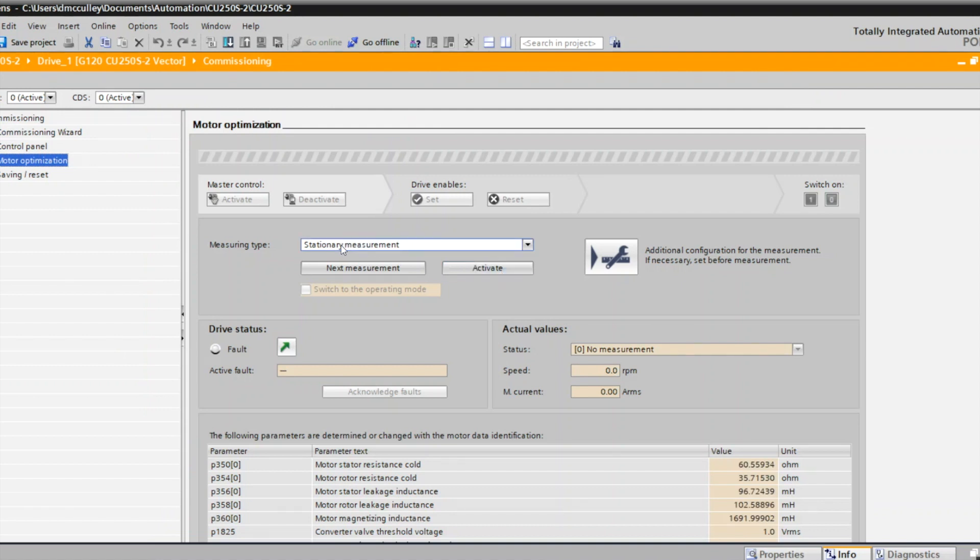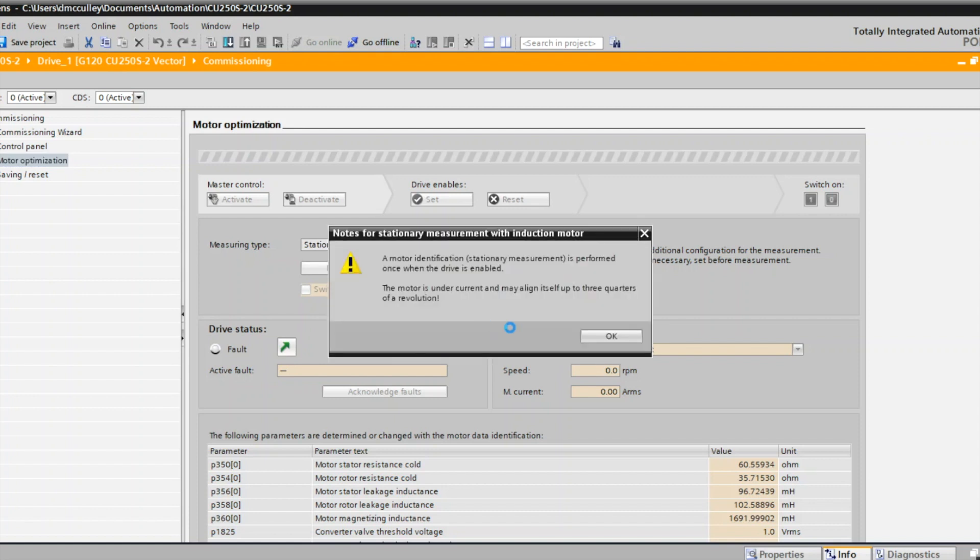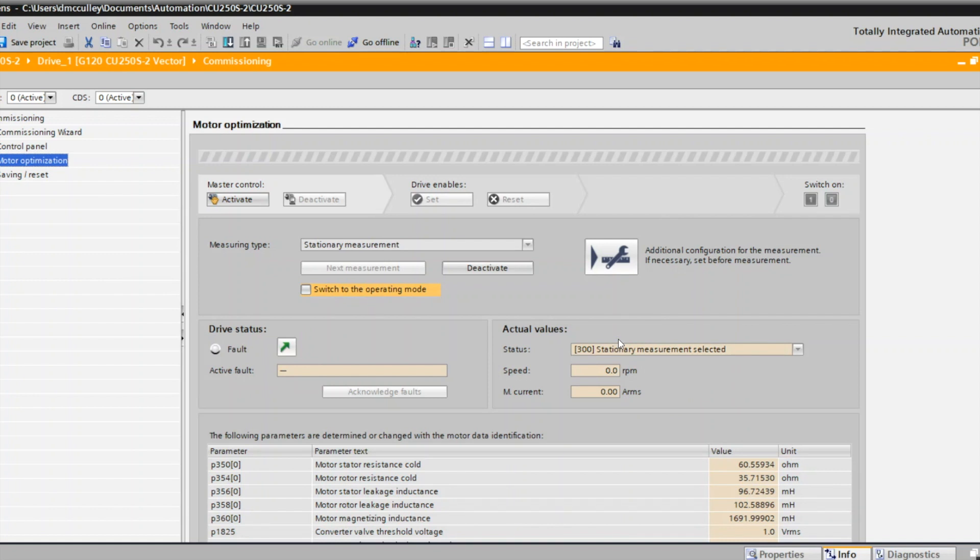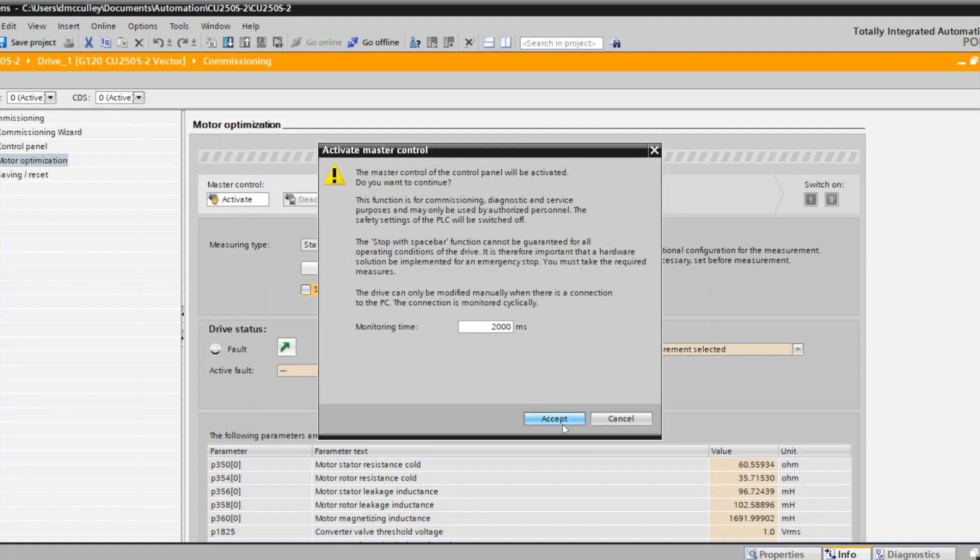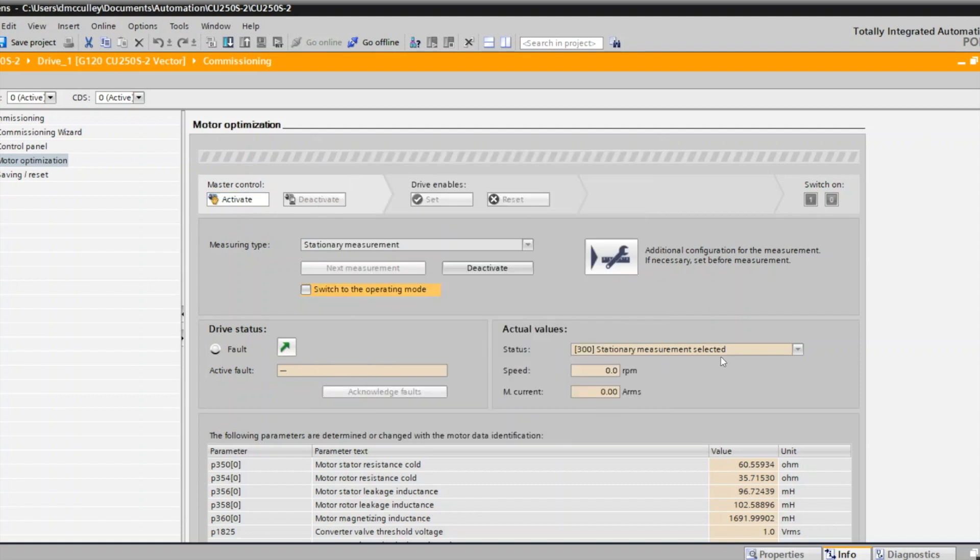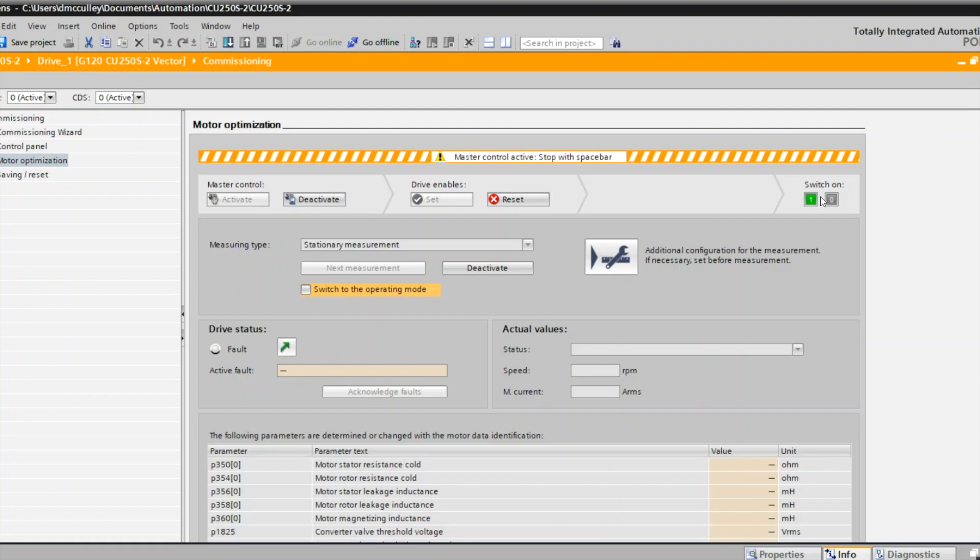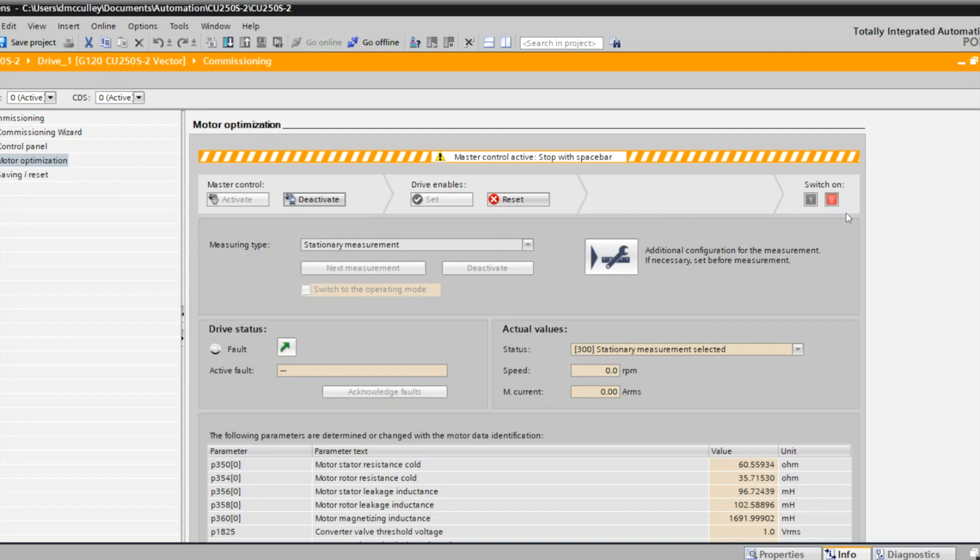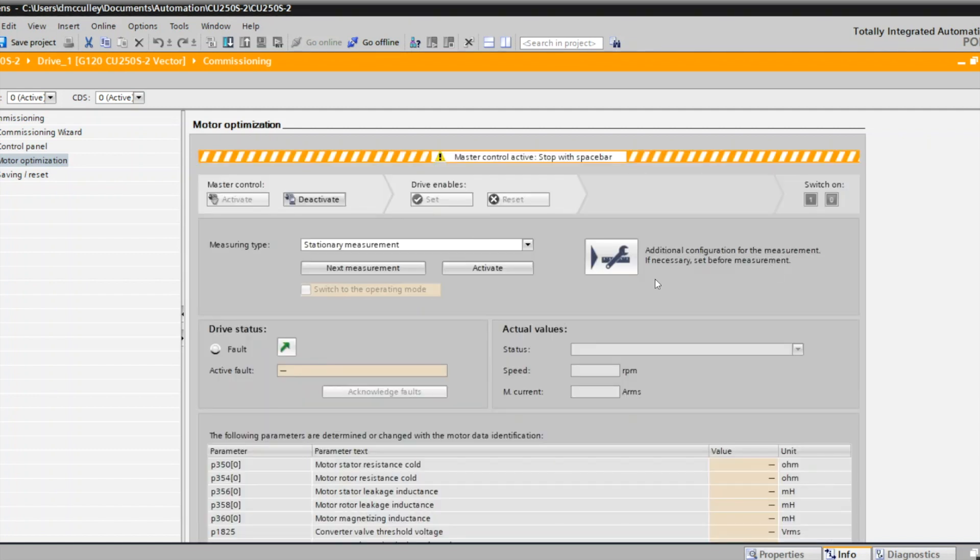I have stationary measurement that I can choose. I'm going to activate that. I actually do not have a motor, so I can't perform these. I'm showing you what you should do. Once you activate the measurement, you activate the master control, and then you get your green switch on, turn it on, and then it'll run through the motor ID procedure. Again, I don't have a motor, so I'm just going to stop it. I'll deactivate that measurement, though you wouldn't need to do that because you would wait until yours has run through your entire motor ID.